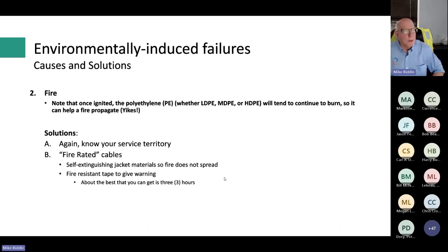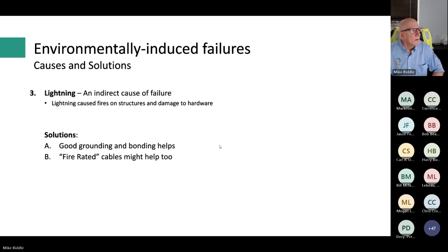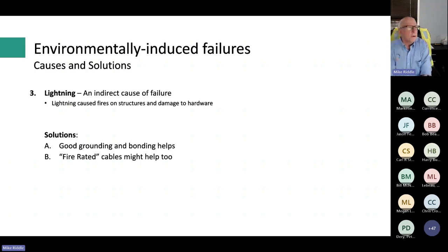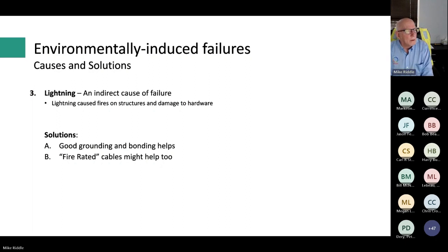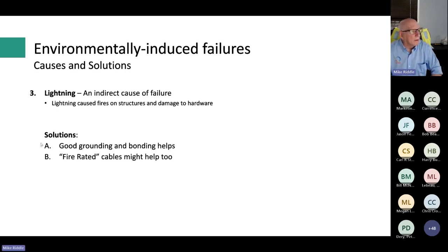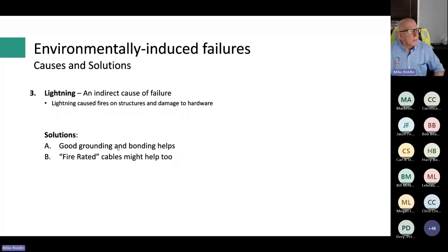Lightning doesn't directly affect the cable much. From what's been documented, lightning hits a structure and initiates a fire, which then damages the cable or supporting hardware. Good grounding and bonding helps improve lightning performance, especially on transmission lines. In areas known to have problems, fire-rated cables may also help.